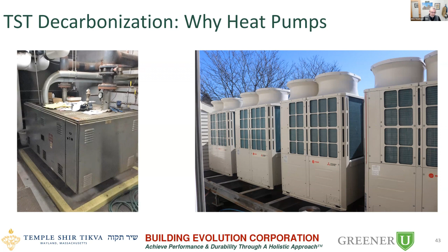Why did Temple Shir Tikva and other projects go heat pumps? When you look at Temple Shir Tikva, shifting that natural gas heating, 85% of the natural gas that was there got shifted off to electric, all to high efficiency heat pump heating and cooling. A small amount of the actual building remained on natural gas. Richard did point out that a small little baby boiler remained on site. The only reason that remained was because the electrical grid for the building could not allow for any more electrical consumption without upgrading the service, which could have taken a 1 or 2 year upgrade process that we weren't able to wait for.